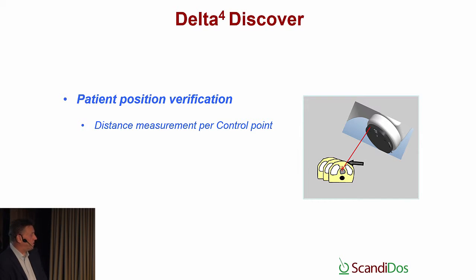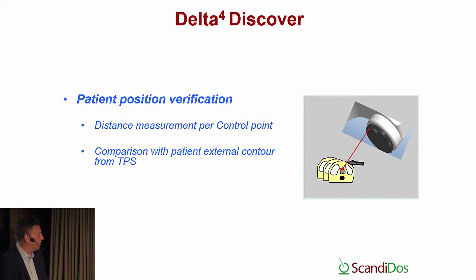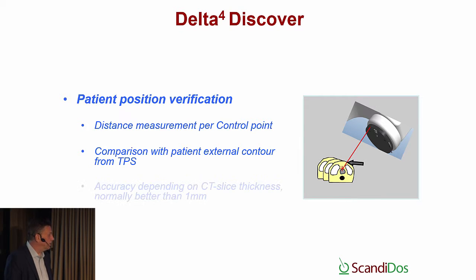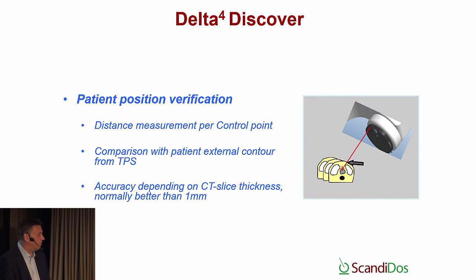Included in the device is also patient positioning verification. It's a laser measuring the distance to the skin of the patient, pointing on the isocenter of the gantry. So it measures the distance per control point, comparing it with the calculated distance from using the CT contours from the treatment planning system, and then of course gantry angle, collimator angle, etc. The accuracy depends on how good accuracy we have from the CT data, so depending on the CT data slice thickness. But normally it's better than 1 millimeter, so it's very, very good.